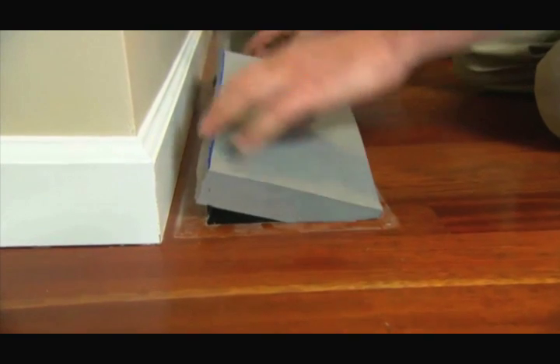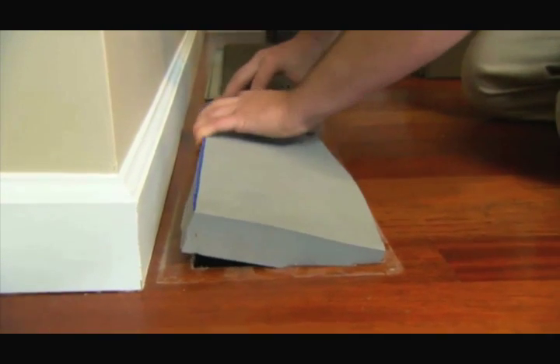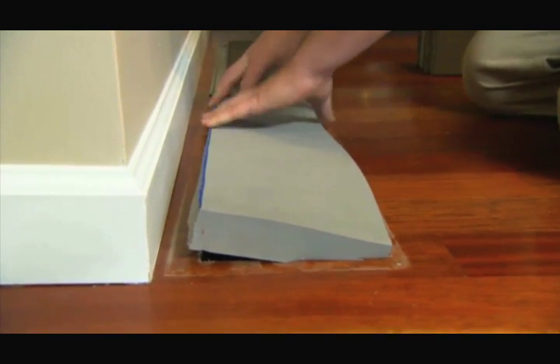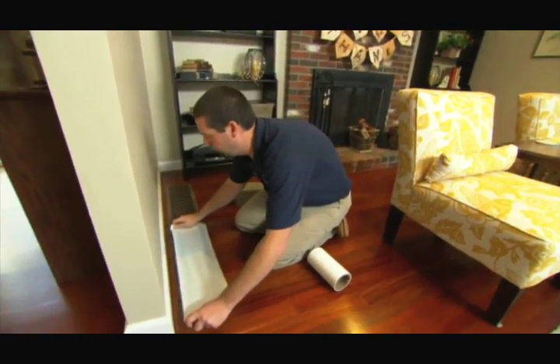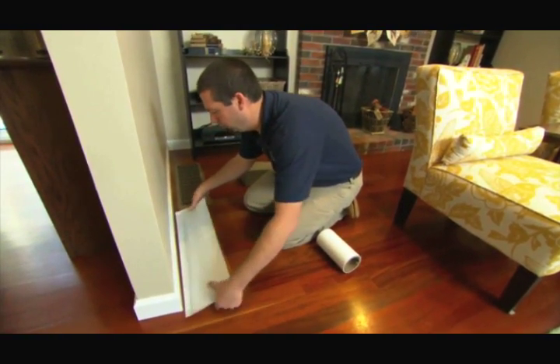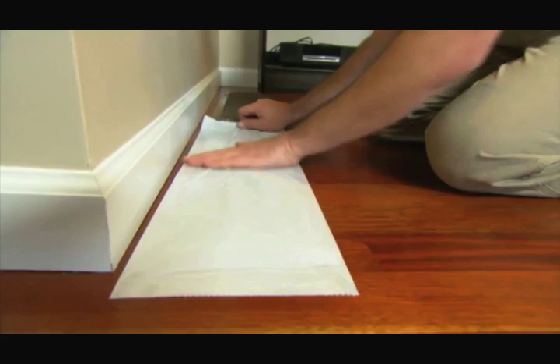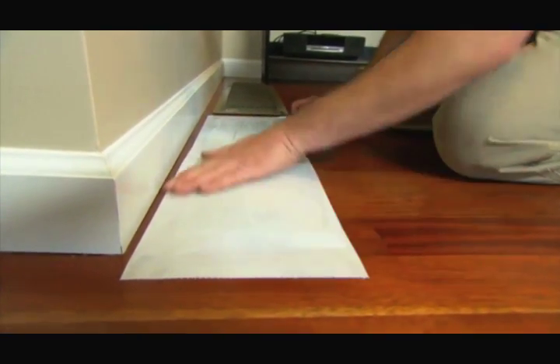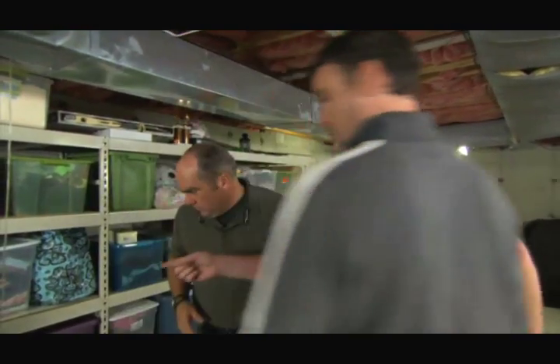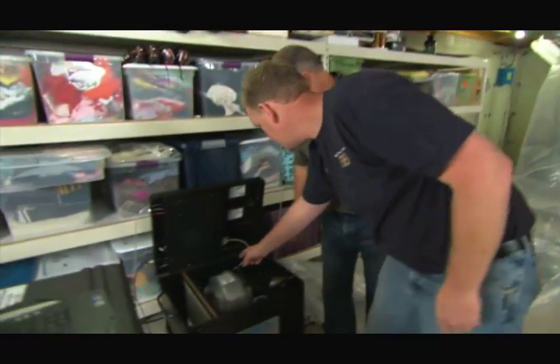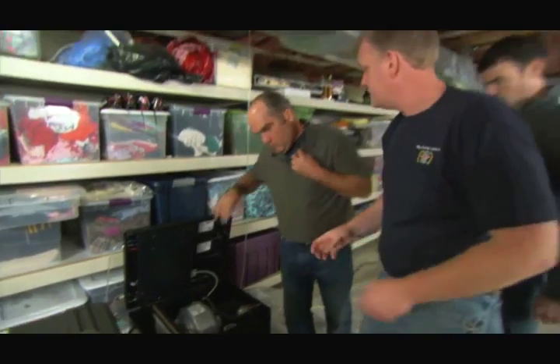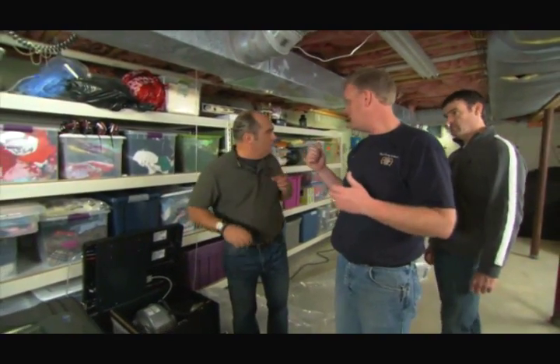So we've already started upstairs. We've sealed all of the supply and all of the return registers. So now any leakage that we measure is coming just from the ductwork. Okay, great. And then you tested the ducts? We did. We ran a pre-test. We used the fan in this box to blow air into the duct system and see how much air is going to leak out. So that pressurized the ducts, and you got it tied into the computer here. Correct.